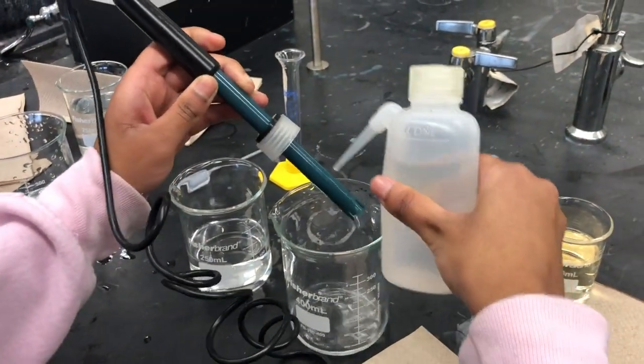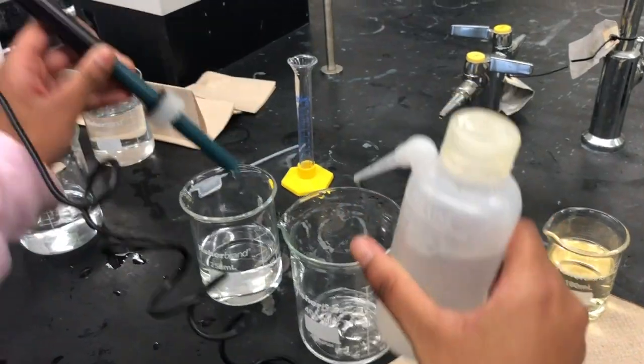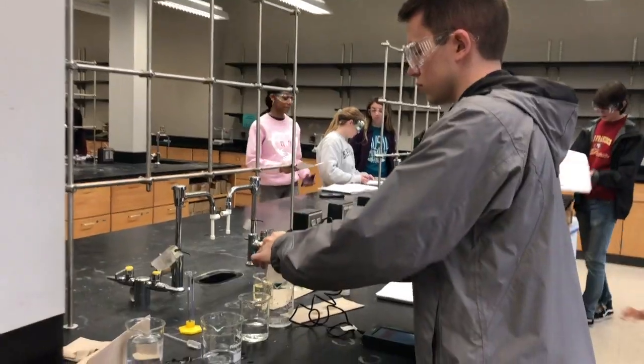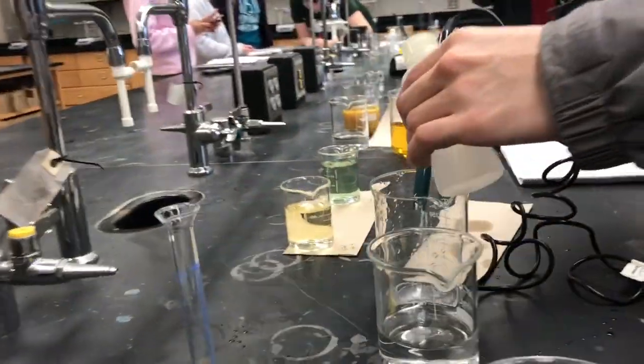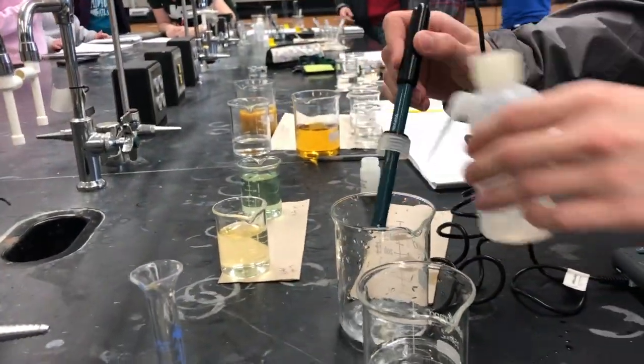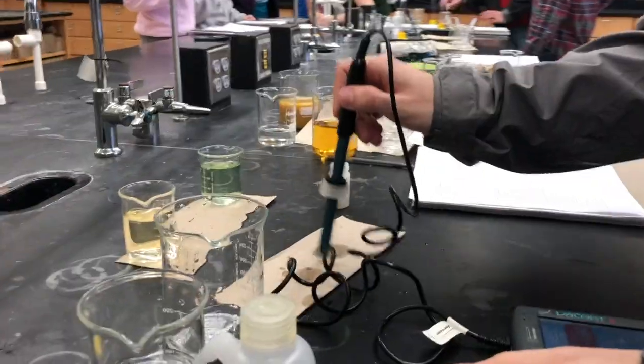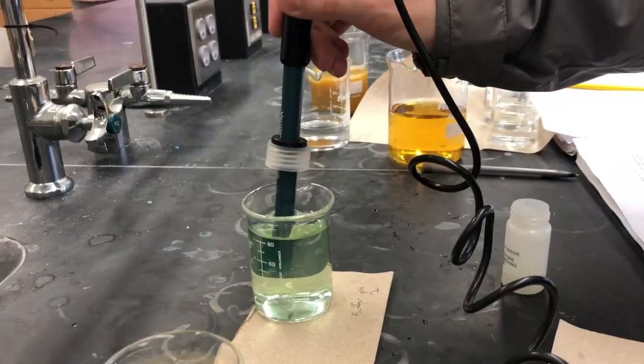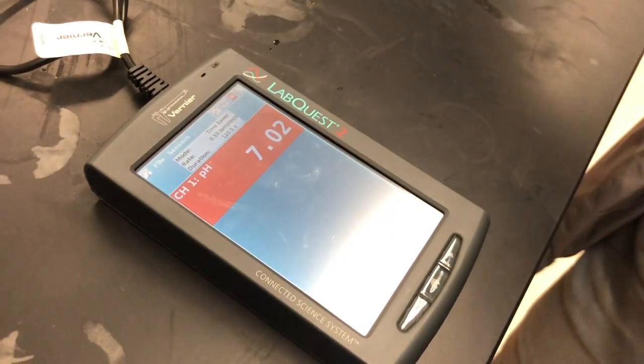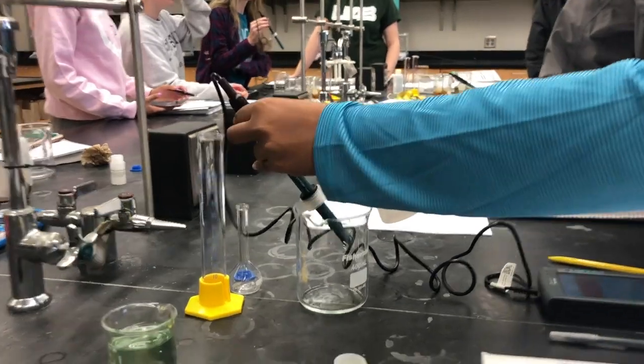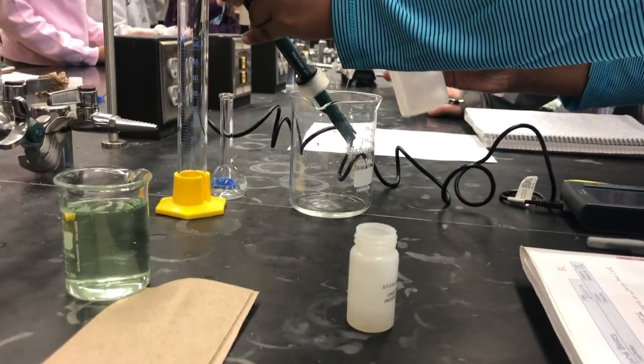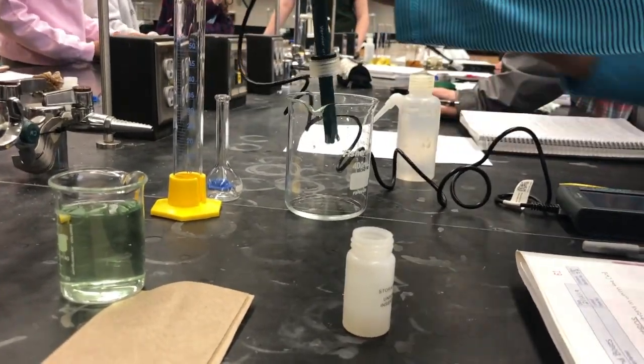Then wash the probe with distilled water into your beaker and place it into a beaker of distilled water to store. Now to double check the calibration, we will rinse the probe off again and stir it into the buffer of a pH of 7. Then we will check if the reading reads 7.0. If this reading is accurate, this means that your pH meter is calibrated and ready to use.